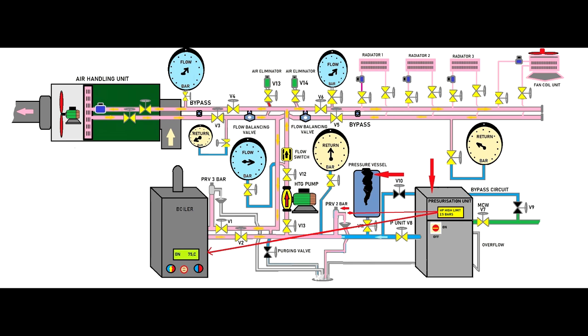Setting up the higher limit above the pressure relief valve, the PRV. And as you'll see on this picture, the PRV is leaking hot heating agent into the drain. And just imagine what happens if that drain will be blocked to one point - you will end up in a disaster.